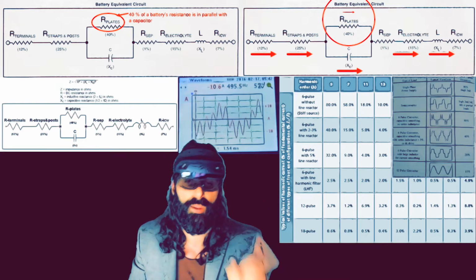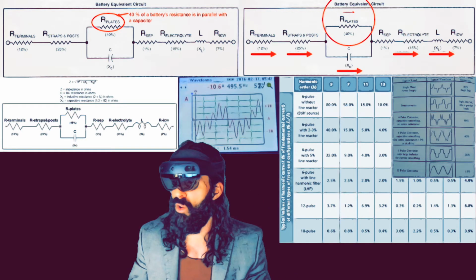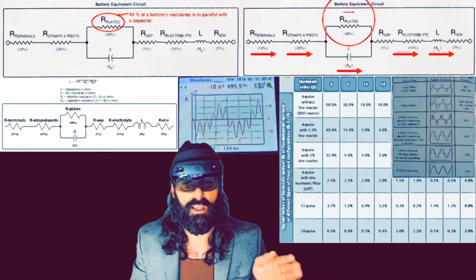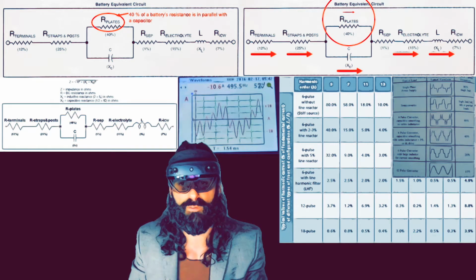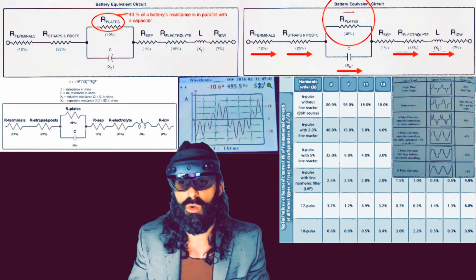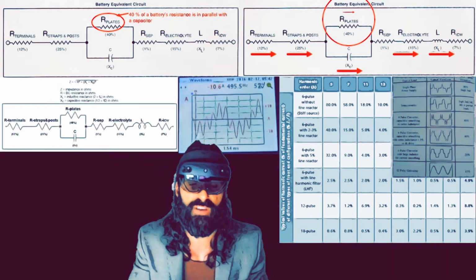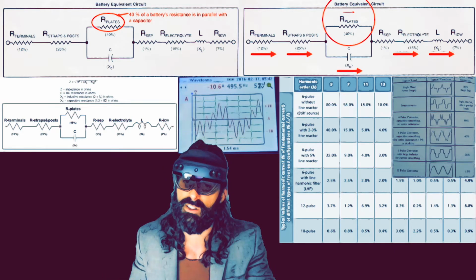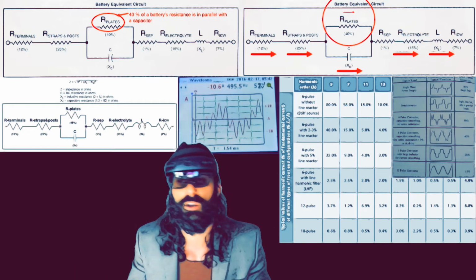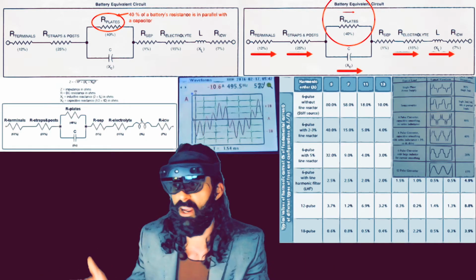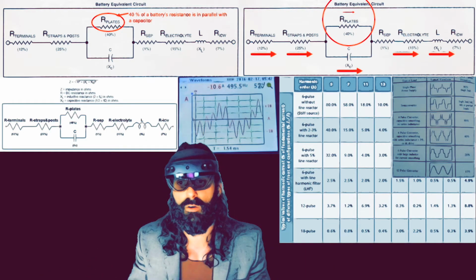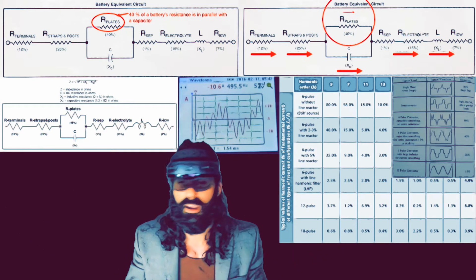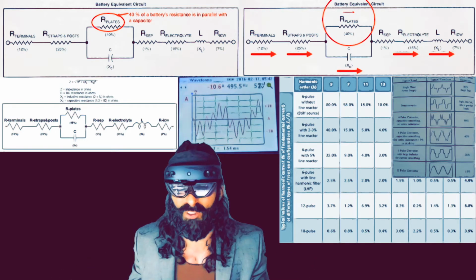But the reason this is important, let's just choose a 12-pulse rectifier. The noise on those systems is generally, for the harmonics, the 11th and 13th. Those are the fundamental frequencies times 60 hertz. If you have a 6-pulse rectifier, you would have harmonics on the 5th and 7th harmonic, so you'd have around 300 hertz. This is important to understand, because when you're designing the monitoring system and they're using various frequencies to apply across there, if those frequencies are fundamental components of 60 hertz, it's not going to work at all, especially if you have noisy DC bus systems. It's going to completely evaporate in the noise floor.